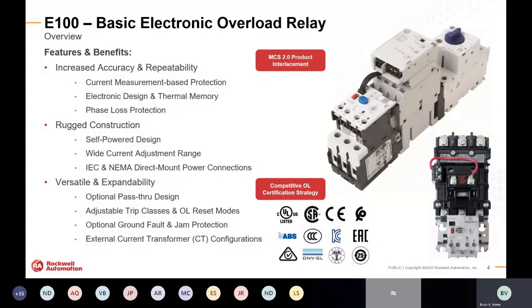In general, the E100 is very versatile and expandable, with an optional pass-through design. So if you don't want to do the wiring or direct connect, you can use the version that simply passes the wires through the openings of the overload without any termination points. It also has adjustable trip classes, different overload reset modes, and optional ground fault and jam protection.